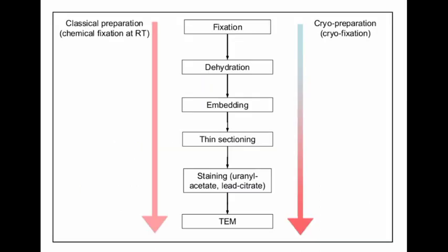And finally, sample preparation. As we have discussed in the earlier section, electron microscopes are run under vacuum conditions. A high vacuum, however, is a very unfriendly environment for biological specimens like cells and tissues, or hydrated organic matter in general. Electron microscopes pose the following prerequisites for the specimen for investigation. First is resistance in the vacuum. Second is electron beam resistance. Third is providing contrast. Fourth is being penetrable for electrons in transmission electron microscopy.